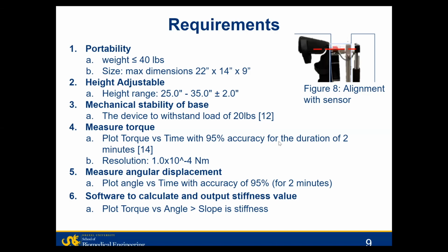The fourth requirement is the measurement of torque over time with an accuracy of 95% at a resolution of 1 times 10 to the negative 4th Nm. Similarly, we also want to measure the angular displacement over time with an accuracy of 95%. Finally, the last requirement is to calculate the stiffness by plotting the torque on the y-axis and the angles on the x-axis, with the stiffness being the slope of the graph.